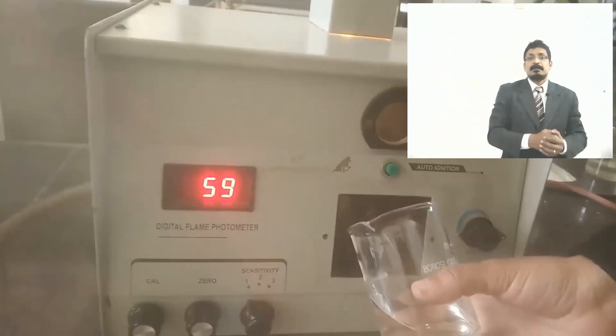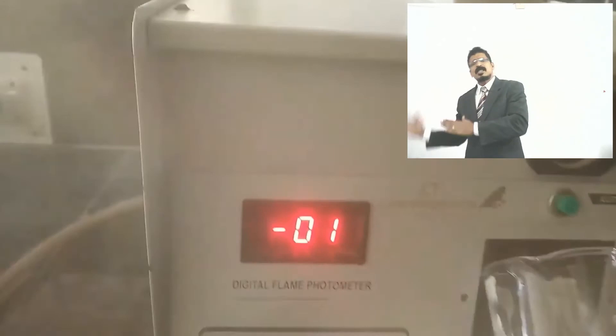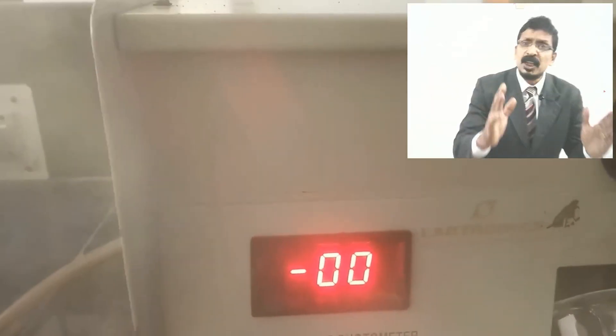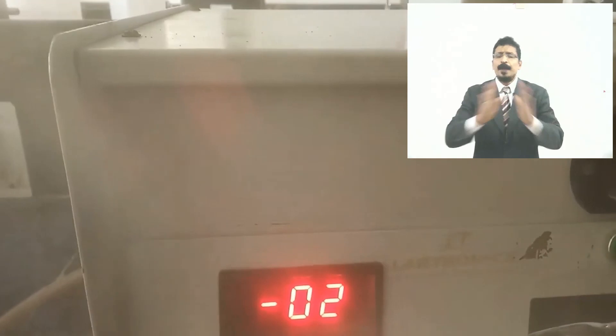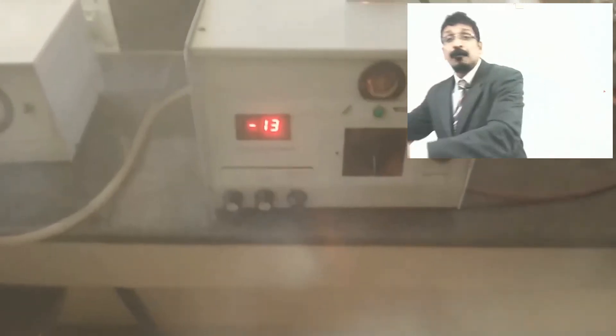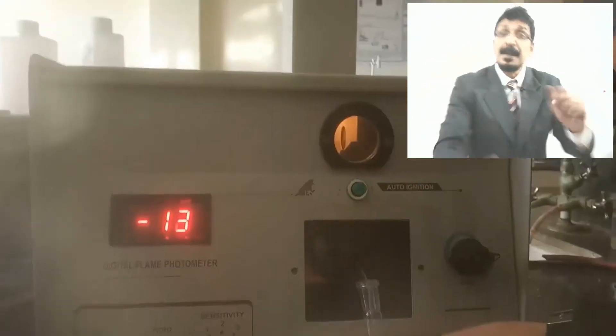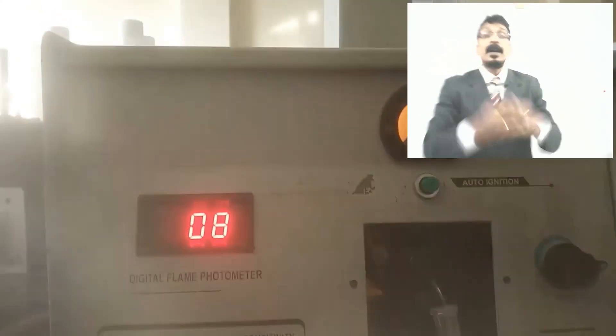Maintain zero with distilled water, then take the highest concentration and set it to a reading of 100. This is a very simple experiment — only you need to know how to fix the LPG gas, how to fix the compressor, and how to maintain the two pressures. Now we will go to the procedure: how to prepare the solution. Weigh 100 mg sodium chloride and prepare a series of standard flasks — minimum 10 flasks — washed, clean, dry, with funnel. Planning is very important.